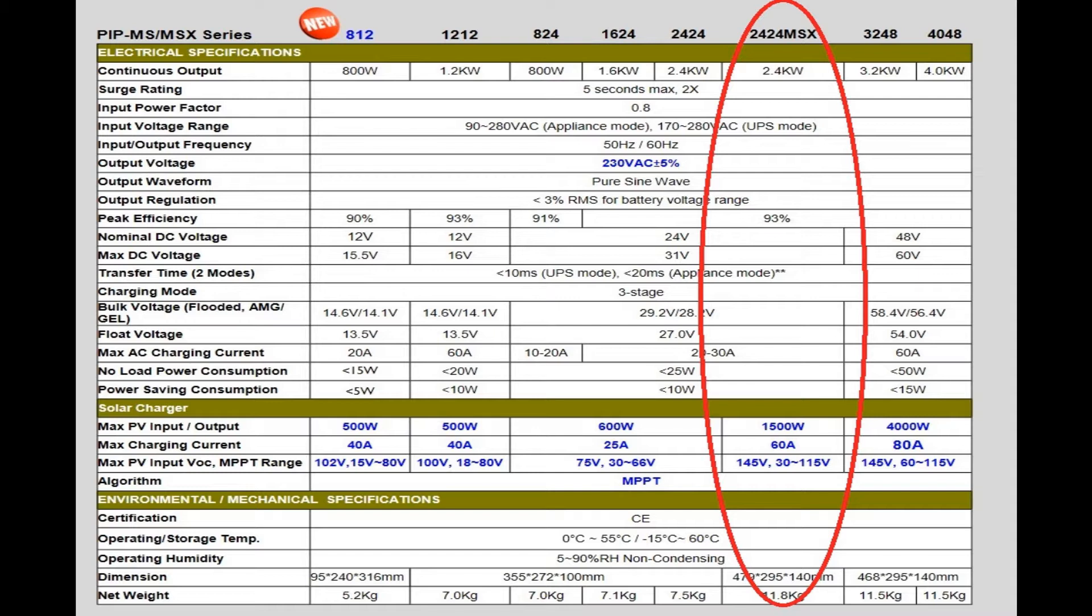Main advantage of an off-grid inverter is that it houses the main functions of a solar system in a single unit. It has a 60 ampere MPPT charge controller, a 2400 watt pure sine wave inverter, and comes with a 30 ampere AC to DC battery charger.